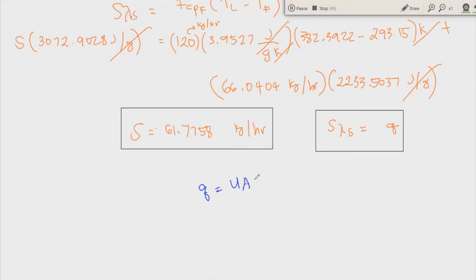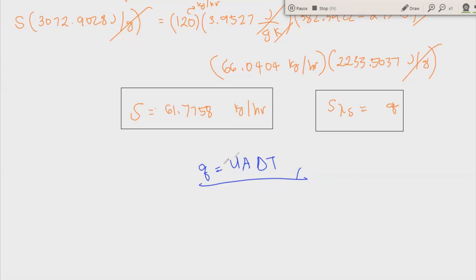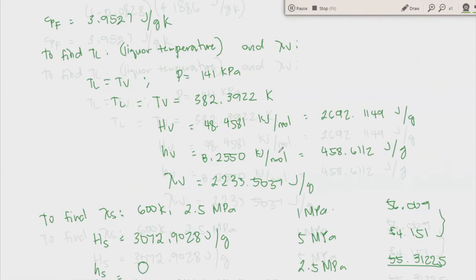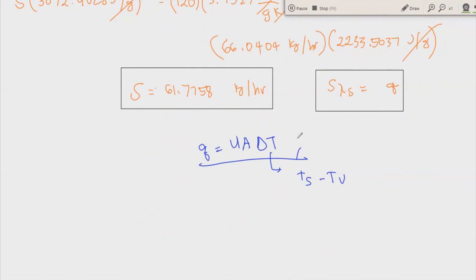For the design equation, Q equals U times A times delta T, where U is the overall heat transfer coefficient, A is the surface heating area, and delta T is typically the difference between the steam temperature and the vapor temperature. If you are given U, A, and delta T, you can find Q directly, and then find S from the steam conditions.